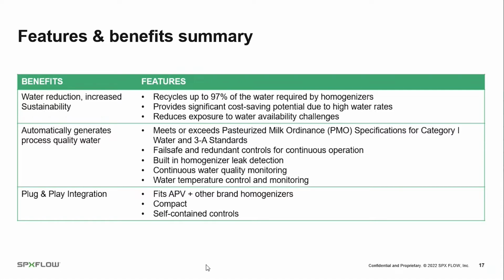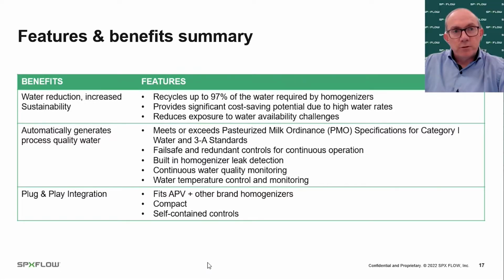Second benefit is that it generates process quality water automatically. And the system has been designed and proven to meet or exceed pasteurized milk ordinance, PMO specifications for Category 1 water, and 3A standards. So the water quality is of the same process quality as you'd expect. The system is provided with fail-safe and redundant controls for continuous operation. Again, uninterrupted operation of your homogenizer. An additional benefit is the built-in homogenizer leak detection through the sensing of the water that's collected in the tank skid. And the system has the continuous water quality monitoring to ensure that the water is of the correct standard throughout the operating cycle.